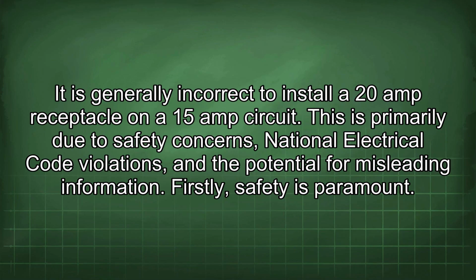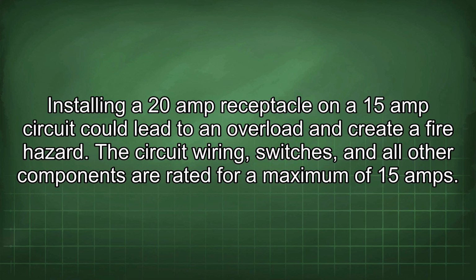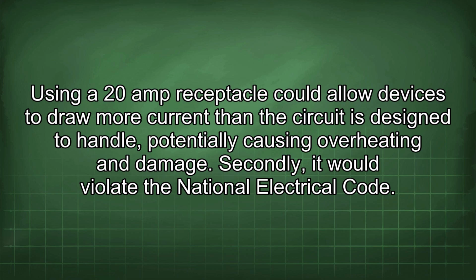It is generally incorrect to install a 20 amp receptacle on a 15 amp circuit. This is primarily due to safety concerns, National Electrical Code violations, and the potential for misleading information. Firstly, safety is paramount. Installing a 20 amp receptacle on a 15 amp circuit could lead to an overload and create a fire hazard. The circuit wiring, switches, and all other components are rated for a maximum of 15 amps.